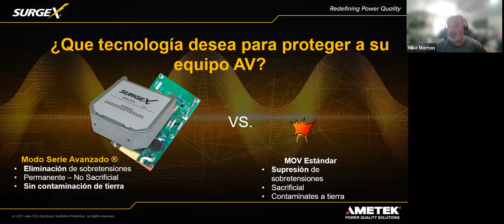The reason we don't get involved with the ground is because microprocessors always have to calibrate on each type of scenario that they would engage in a new process. So they always look to ground, which is the most stable environment, and it should have 0 voltage. If it's been contaminated with a surge that has been shunted or sent to ground, then you have issues with that particular type of calibration, which can cause things such as, again, lockups and reboots.